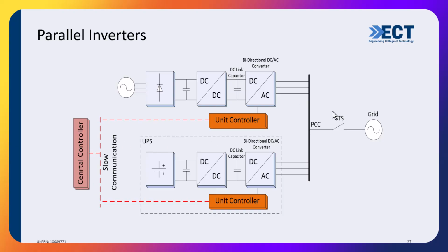So we have that switch: if it's on, that means I can sell power to the grid, or consume power to charge my battery. If the grid is not there, that unit and that unit should be aware — that's why we need islanding detection. They also have to manage power between themselves to supply a load, or to charge a battery. If that battery is fully charged and we don't want any more power, they need to manage themselves to switch off or reduce that power. Without doing this, the bus will go unstable — the hertz and the voltage will both start tripping. So some management between them is very much needed.